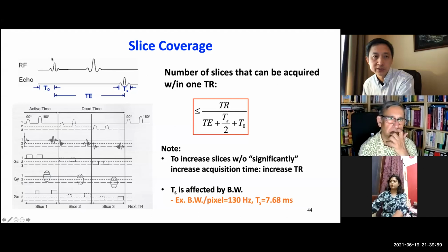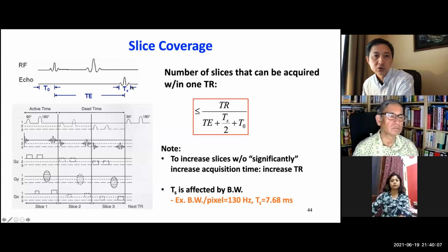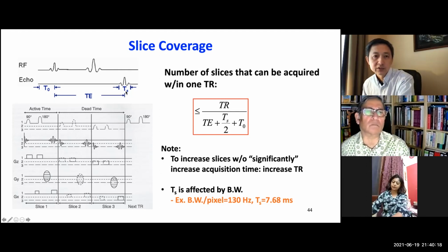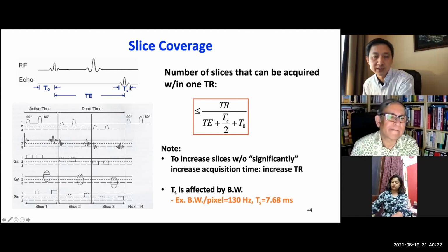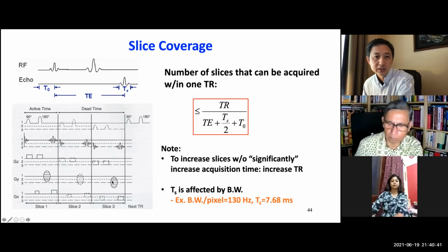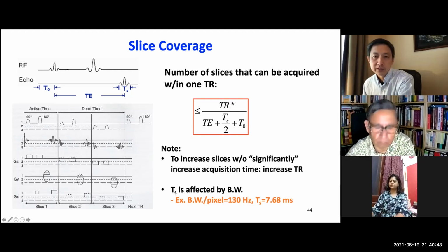Here I'm showing you a spin echo sequence. So 90, 180, and then we read the signal. To complete the whole process, we need a T0. T0 is just a preparation time. It's typically very small. And then TE, echo time. Echo time is at the center of the echo, so we still have half of the sampling time. So to complete the whole process will require TE plus T0 plus half of TS. That's here. And within the same TR, we can acquire multiple slices. This is 1 slice, 2 slices, 3 slices, and then that's the next TR. So the number of slices that can be acquired is TR divided by the time required for 1 slice.